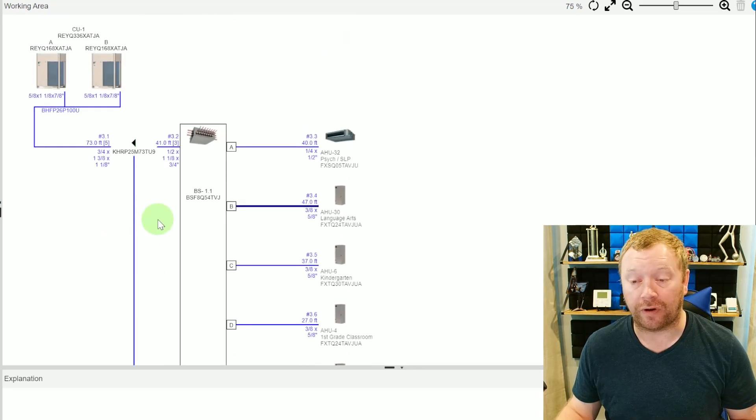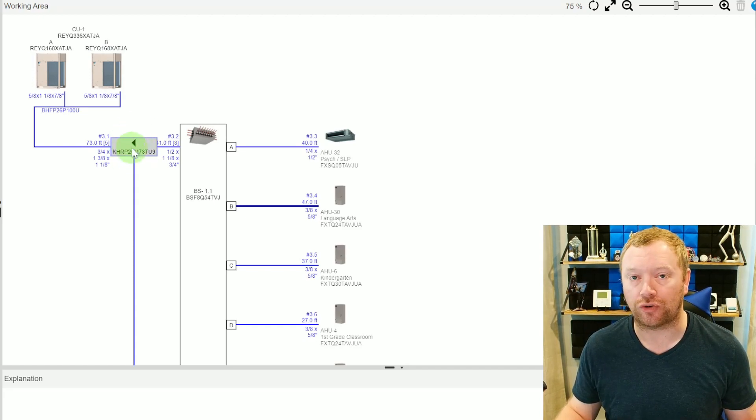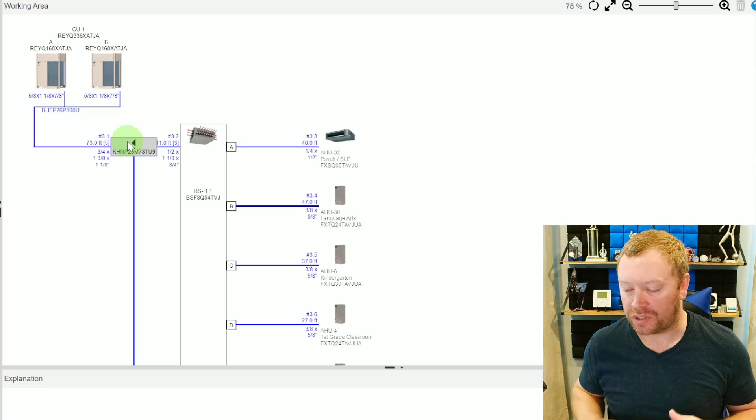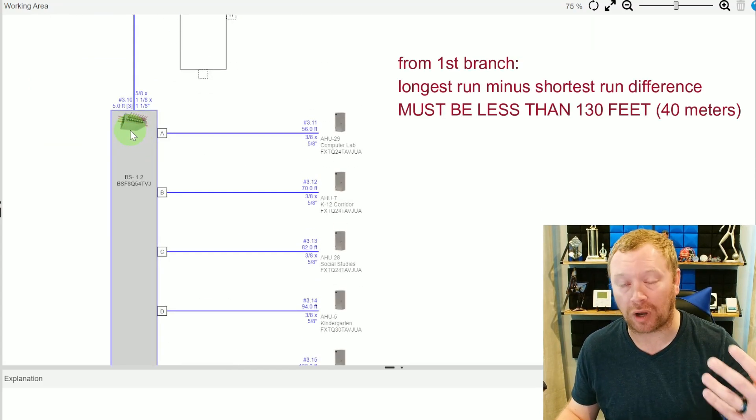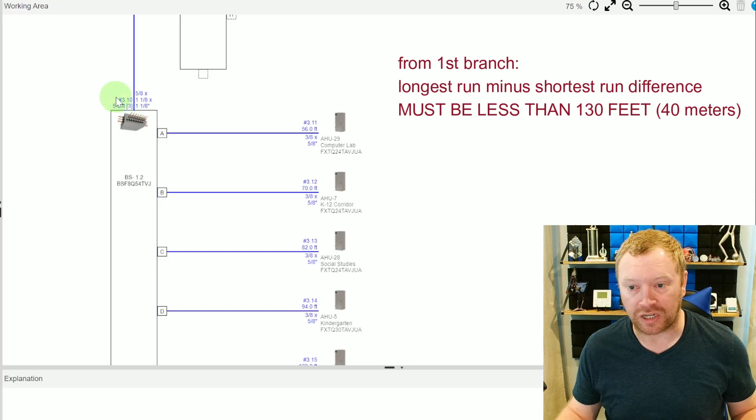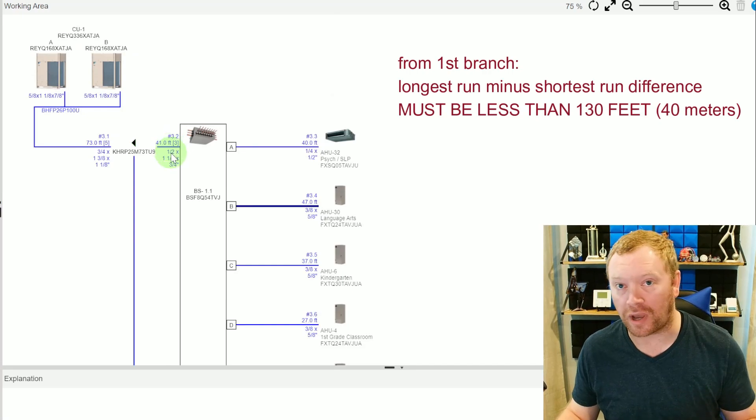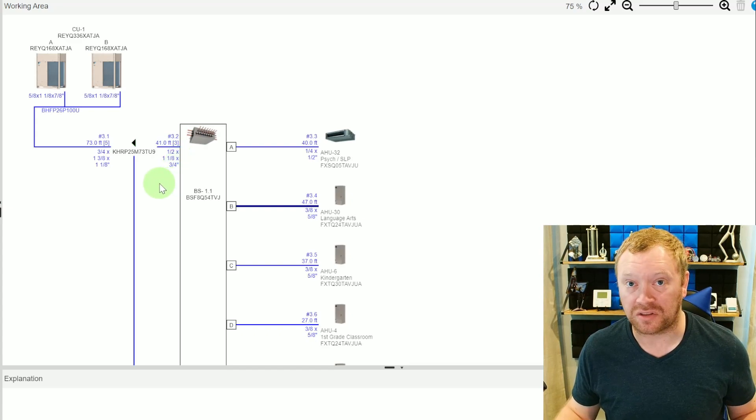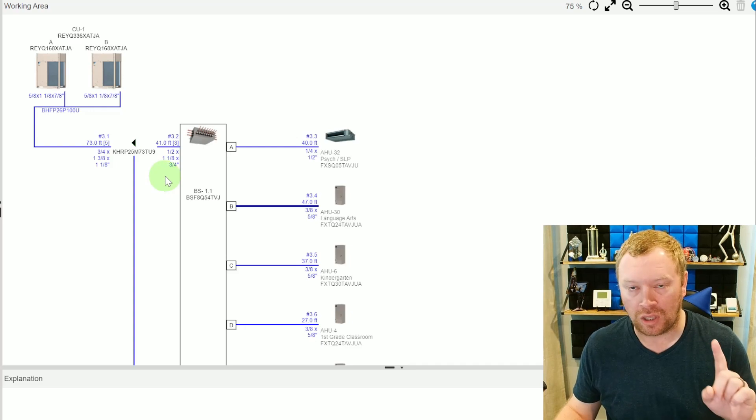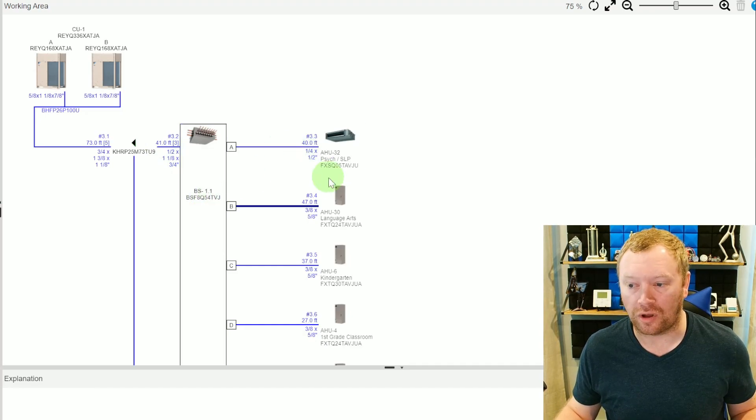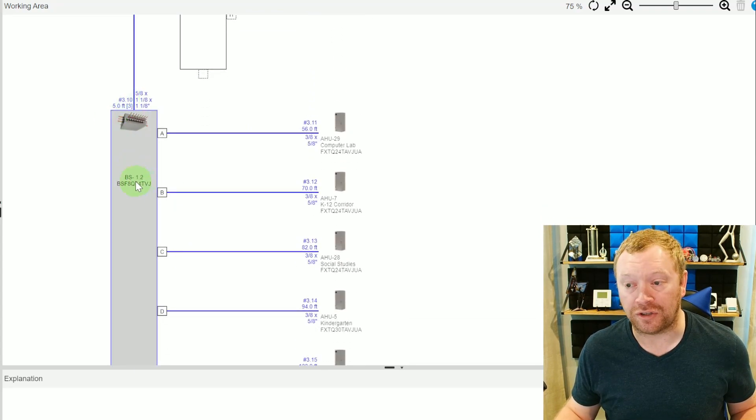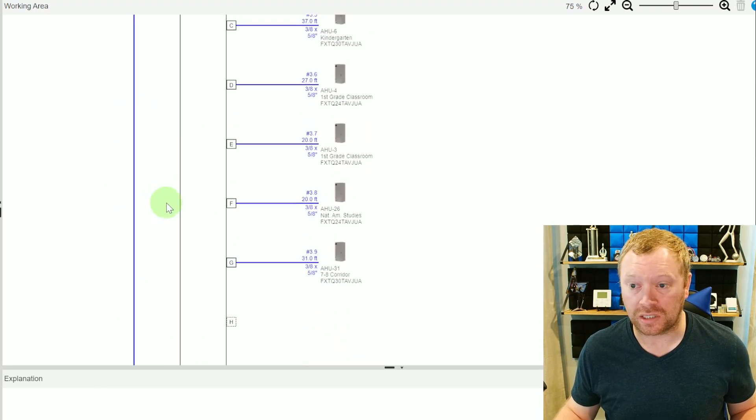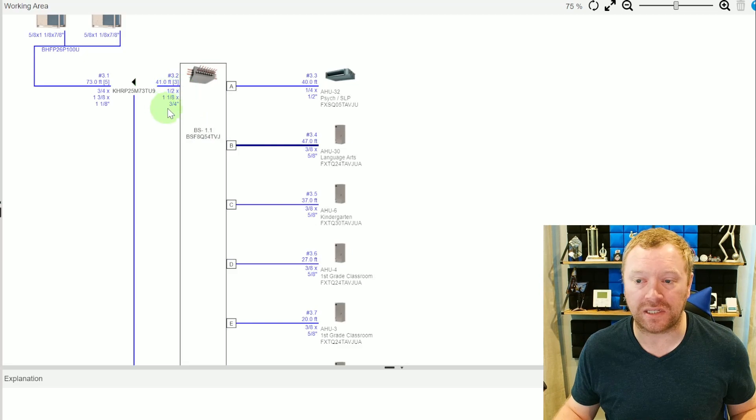One thing that happens very commonly is when you guys have a set of plans, you're going to notice that that Y branch gets drawn in somewhere that balances out the system. We don't often like to come off of a branch and immediately hit a branch box, depending on the lengths, depending on how many boxes we have, giving you a very generalized example here, but coming off of a branch and going five feet to a branch box, we don't like to do that. We want to have our branches and all of our piping as balanced as possible within the system.